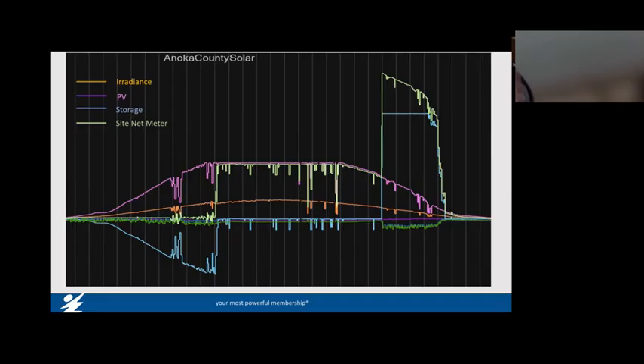So a couple of operational details here: we maintain a resting state of charge not greater than 50%, we have a limited number of cycles we can do per year—75 cycles per year—and we're not supposed to keep them charged above 50% for any longer than 24 hours at a time.